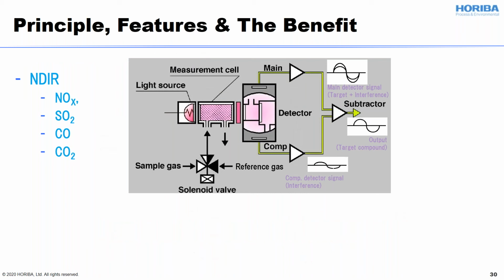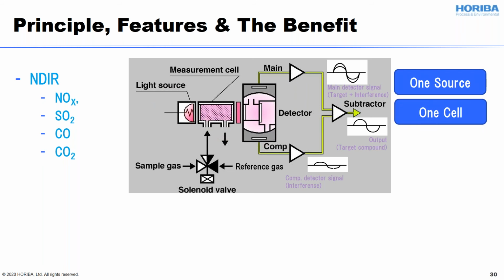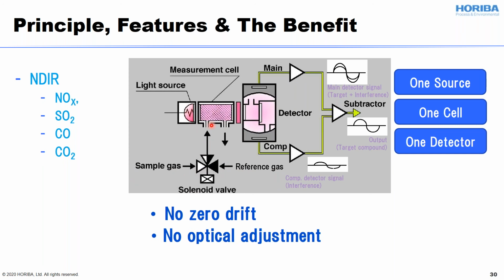So HORIBA developed a way which consists of one light source, one measurement cell, and one detector. The reference gas is introduced like this, and right after that, the sample gas is introduced like this. So we are alternately introducing the reference gas and the sample gas, reference gas, sample gas, every second. That means you are always looking at the zero, and right after that, you are looking at the sample, which is the span, right? So you are doing a kind of virtual zero calibration every second, which means you don't have any zero drift anymore, and you don't have to do any optical adjustment anymore. So this is a great feature that gives us stable measurement.